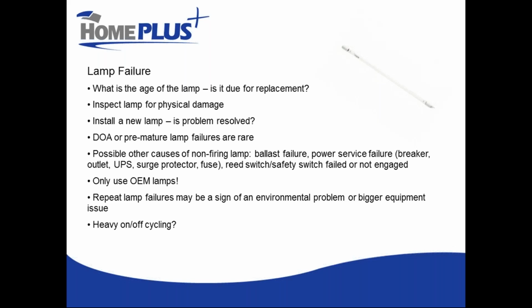Some other things that can cause a lamp not to fire at all could be a ballast failure, a problem with the power supply, or breakers. There are fuses in some of the UV units as well, where the fuse will blow and need to be replaced. Could be a problem with the breakers in your main electrical panel. Could be a problem with the electrical outlet, so try a different outlet.